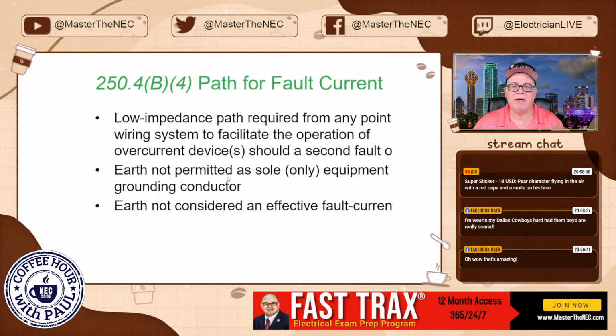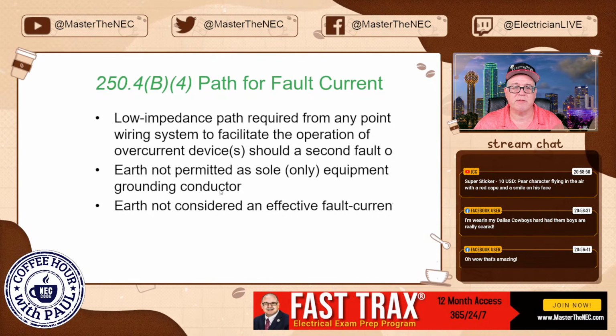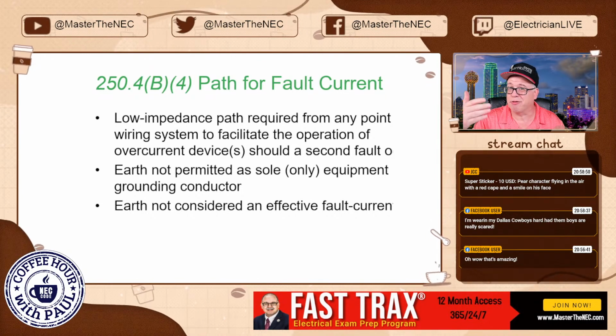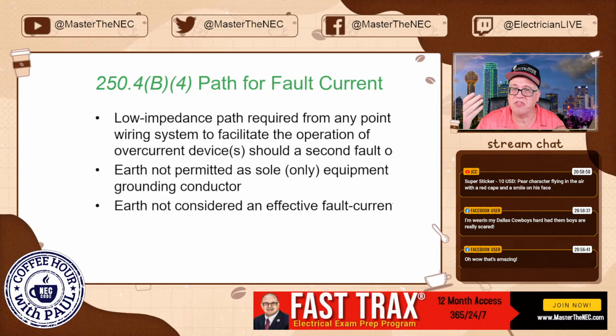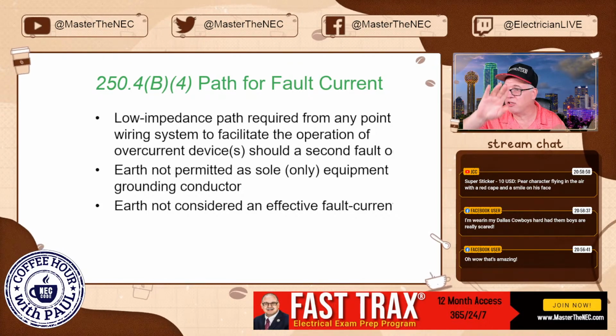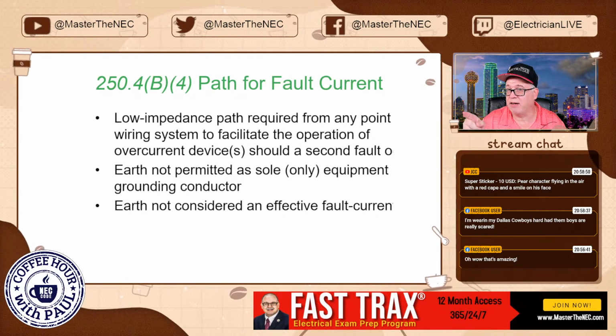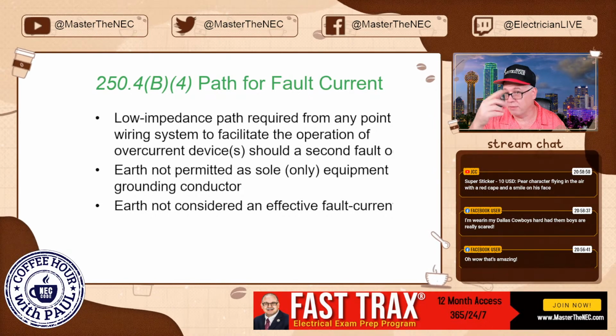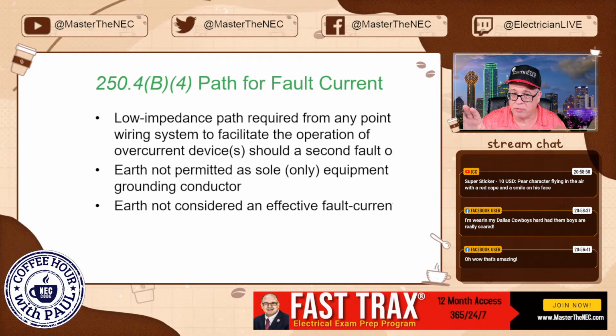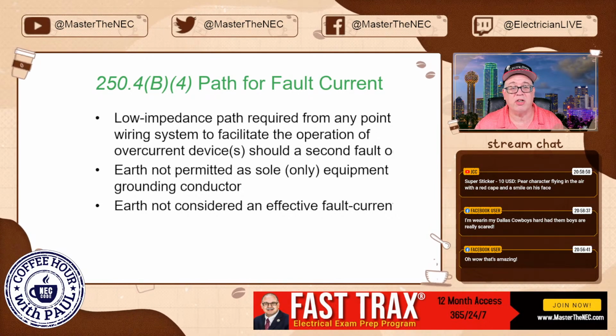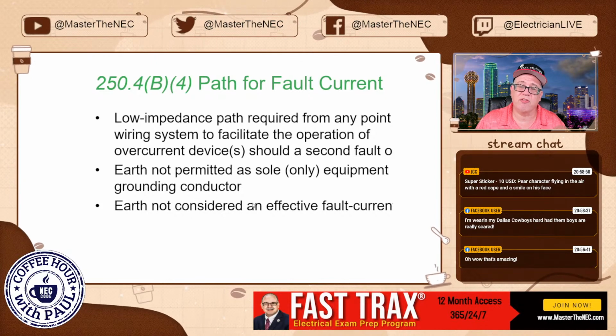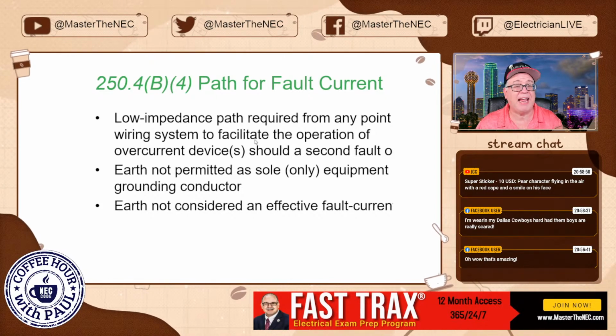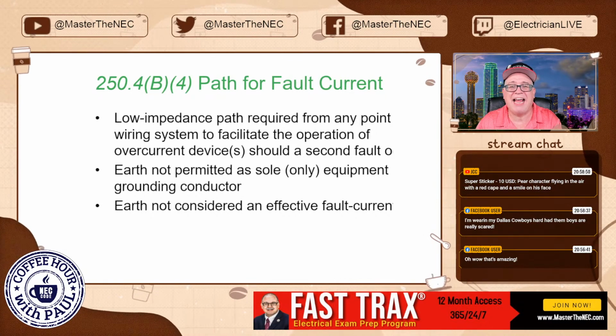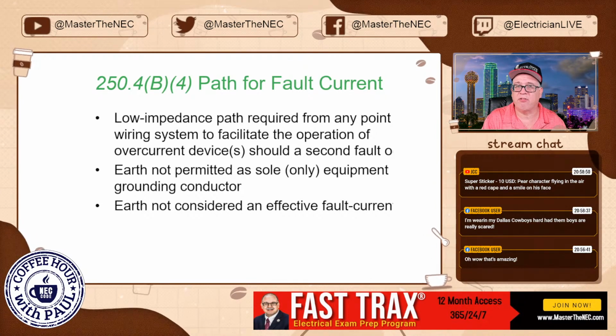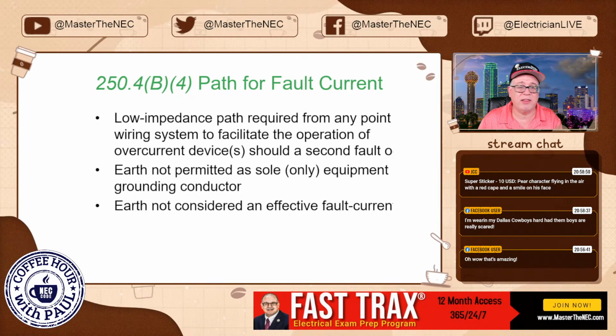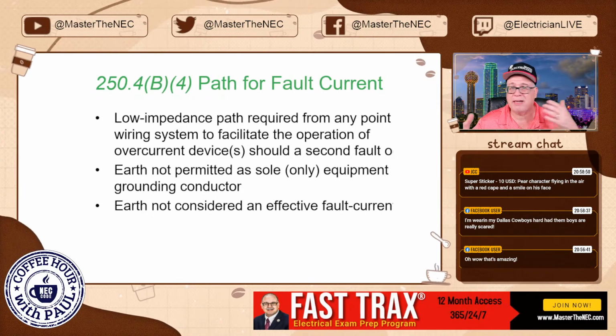Again, earth is not permitted to be the sole equipment grounding conductor. Yes, it might be a redundant path, but again, the resistance is so high, it's not going to do us any good, and you certainly don't want to rely on it. We're not the utility here. We're on the NEC side of acceptance under the scope of what's covered by the NEC, so we don't care about the utility, folks. We're worried about what the NEC says, so we're not going to use the earth. And again, the code reminds us that the earth is not considered an effective ground fault current path. And remember, the code says it has to be a low impedance, effective ground fault current path. We already know that the earth can't be that. So there's no sense in even bringing the earth into the equation, right?